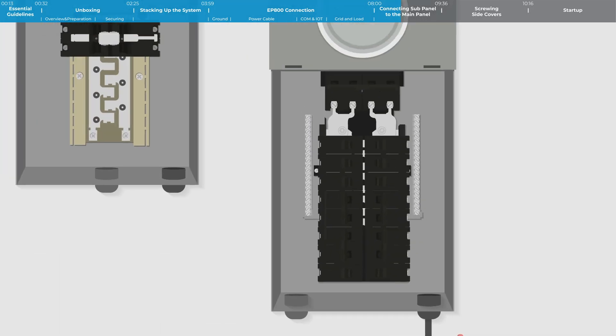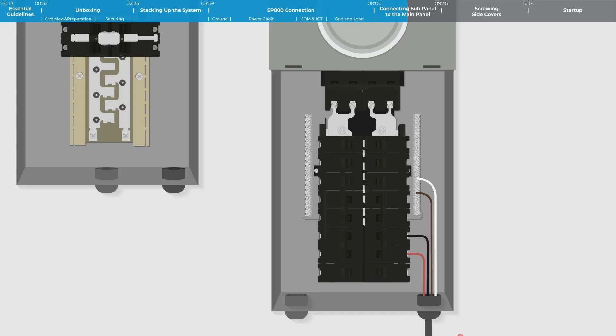Locate a 2P circuit breaker in the main panel. Connect the two live wires from the switch to the breaker. Attach the neutral and ground wires to the ground neutral bus bar.